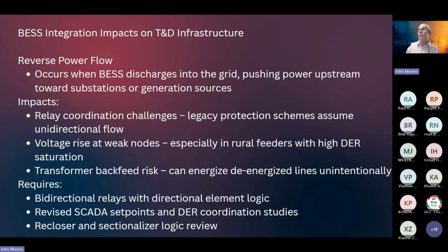And so they're going to cause instability in the voltage on the system. Whereas these battery systems, they're going to put power into the system, not just voltage. And when we backfeed a transformer, we can accidentally de-energize lines, so that can cause outages. And if we have these and we wonder what's causing it, we need to look at what's recently been installed on the system. Have there been BESS projects installed lately? Have there been other data centers or other loads that would cause us this issue? So we address it by revising our SCADA set points, and we look at distributed energy resource coordination studies.